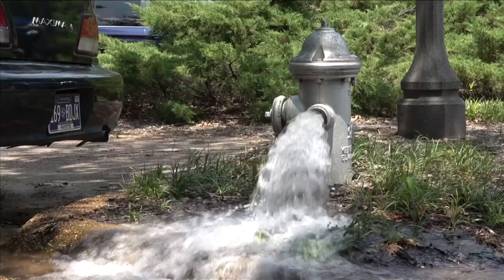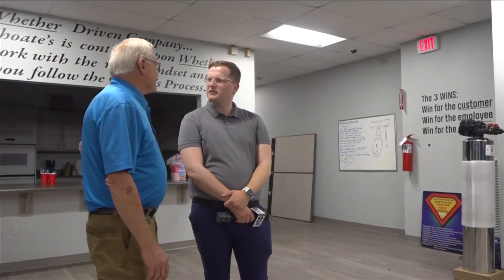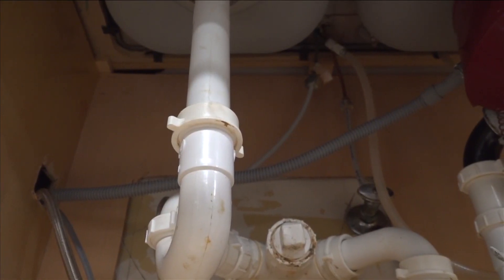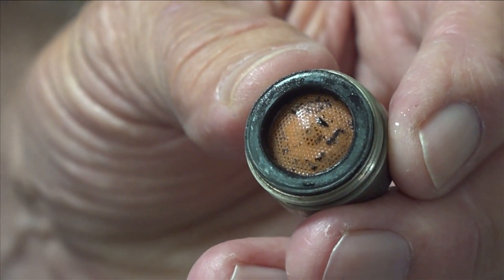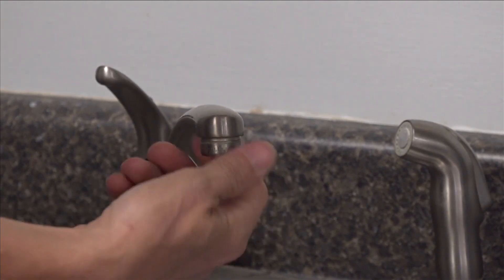Many viewers still wonder: is there any diesel remaining in Germantown's pipes or filters? Randall Lynn with Choate's Plumbing says people need to be cautious over the next few days. Newer homes or plastic piping — it could still remain there. Lynn says there is a chance diesel could clog up the filters if those are still in place when you start flushing. He recommends removing the filter and flushing it, or using a bypass. While you flush, Lynn also recommends removing the aerator at the tip of your faucet.